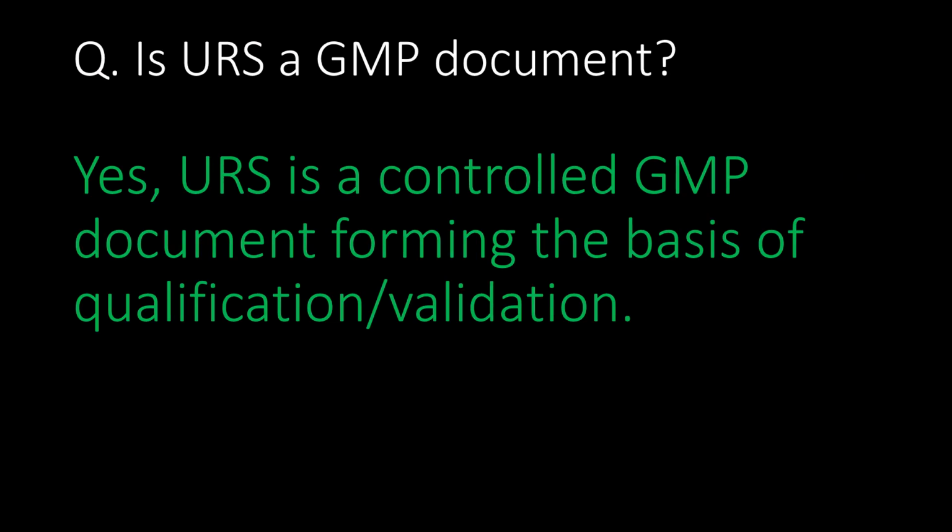Is URS a GMP document? Direct answer is yes. URS is a controlled GMP document forming the basis of qualification or validation.